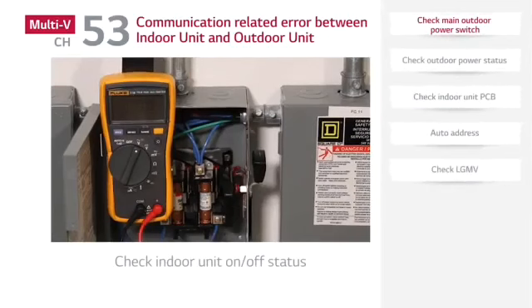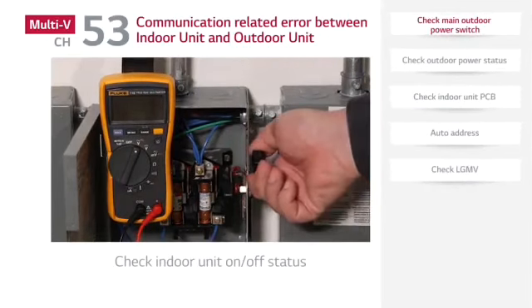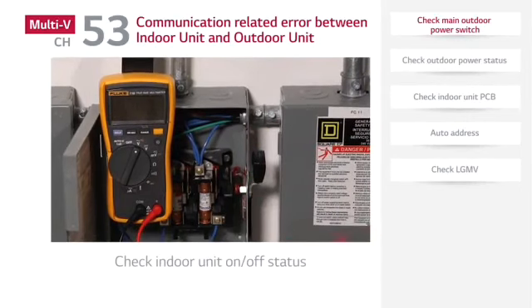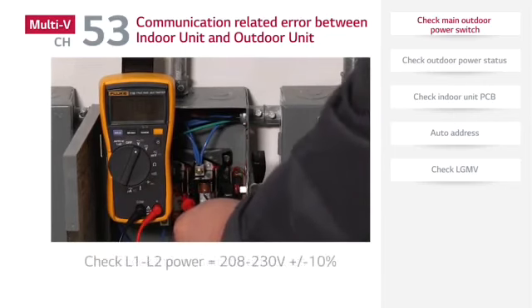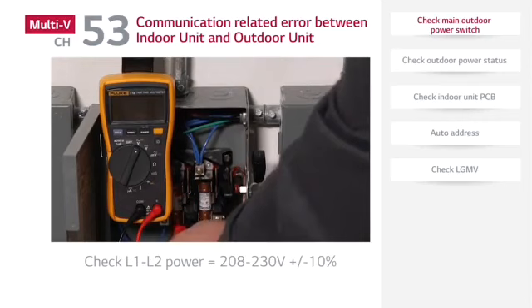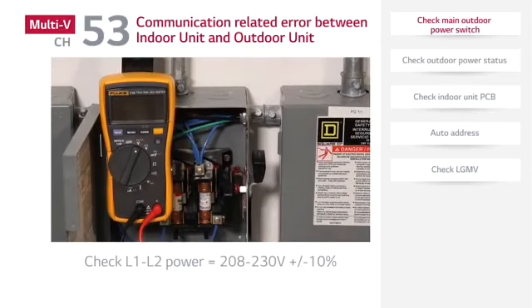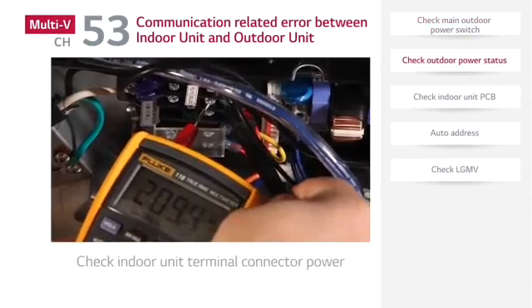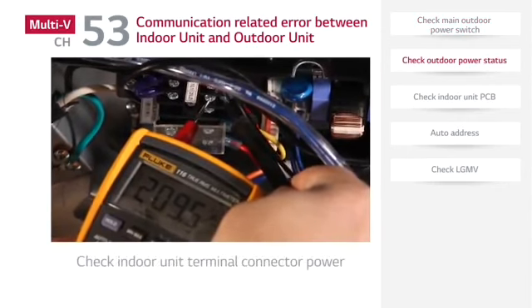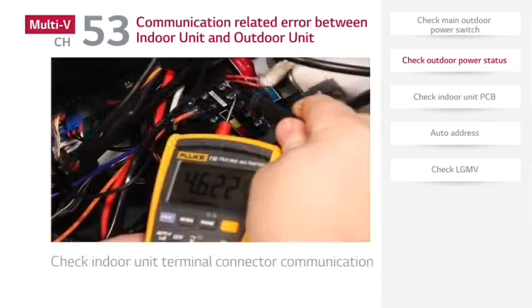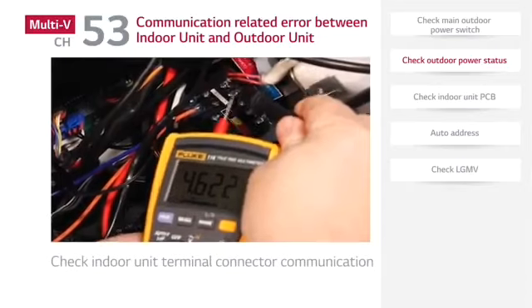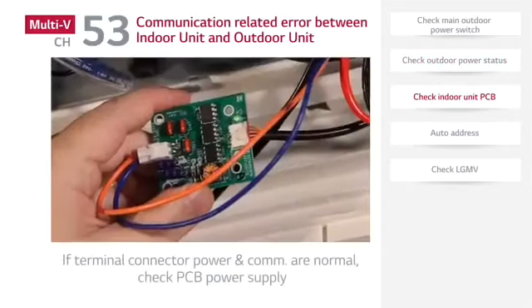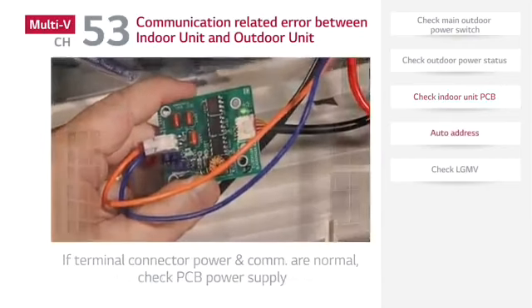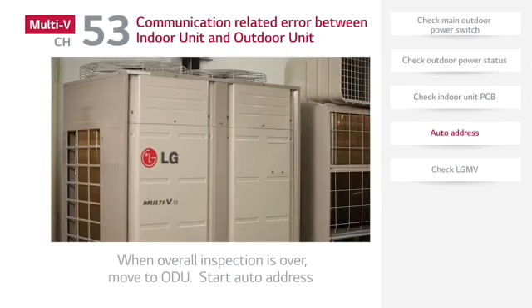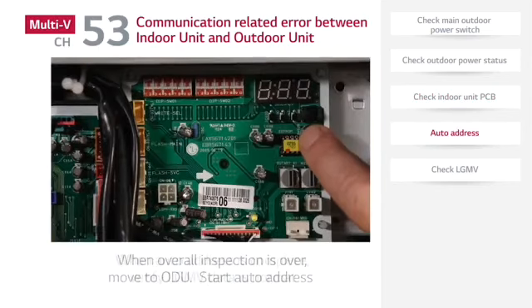If a CH53 error occurs, make sure to check the indoor unit disconnect on-off status. Also check if the indoor unit disconnect output voltage is 208 to 230 volts plus or minus 10%. If the supply power is not within this range, contact a licensed electrician to investigate further. If the power at the disconnect is normal, check the indoor unit terminal connector power and communication. If the terminal connector power and communication signal are normal, check to see if the indoor unit PCB power supply is okay, and whether the indoor unit PCB operates normally. If the indoor unit PCB is normal, move to the outdoor unit and proceed with auto address work.